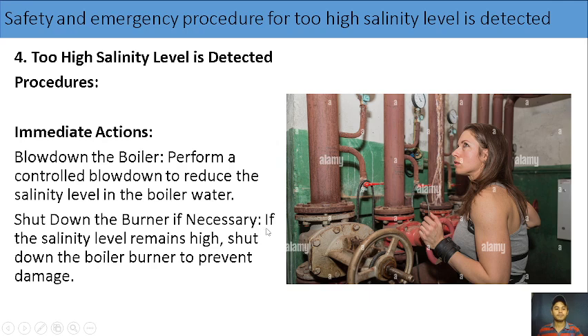So if the salinity is very high, then there is potential foaming or carryover in the steam that will also prevent or lessen the heat transfer from steam to the consumers. So what are the immediate actions? Blow down the boiler, perform a controlled blowdown to reduce the salinity level in the boiler water. So that's the only way. Blow down the boiler. If it's very high still after blowdown, then you may have to replace the water. So shut down the burner if necessary. If the salinity level remains high, shut down the boiler burner to prevent damage.